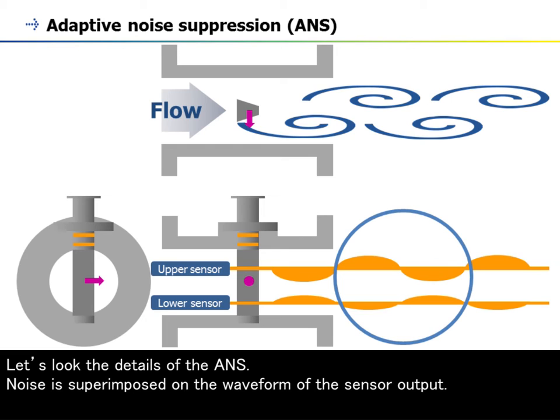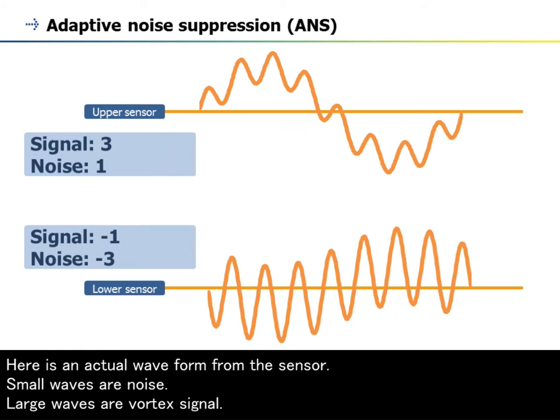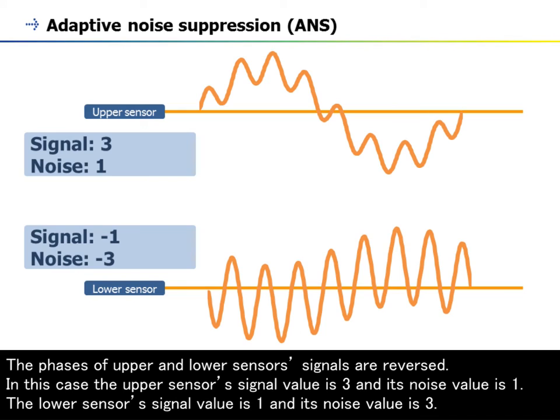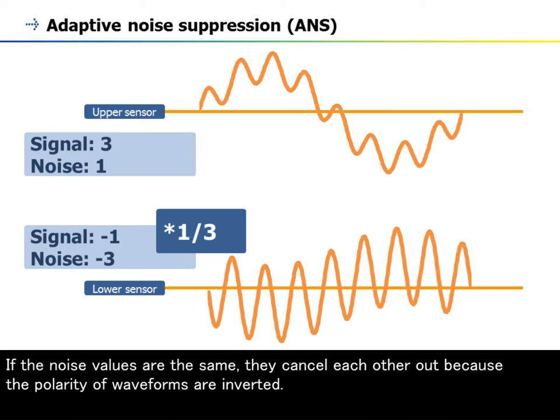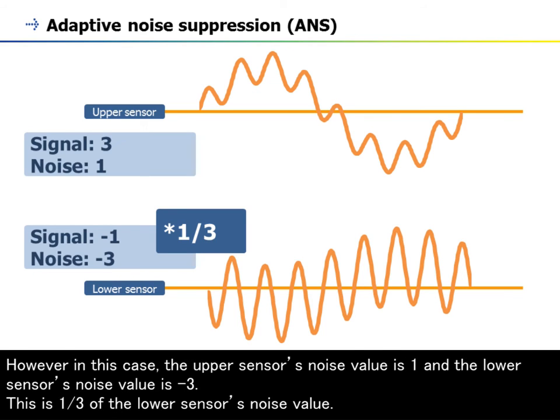Noise is superimposed on the waveform of the sensor output. Here is an actual waveform from the sensor. Small waves are noise; large waves are vortex signal. The phases of upper and lower sensors' signals are reversed. In this case, the upper sensor's signal value is 3 and its noise value is 1. The lower sensor's signal value is 1 and its noise value is 3. If the noise values are the same, they cancel each other out because the polarity of waveforms are inverted. However, in this case the upper sensor's noise value is 1 and the lower sensor's noise value is minus 3. This is one third of the lower sensor's noise value.